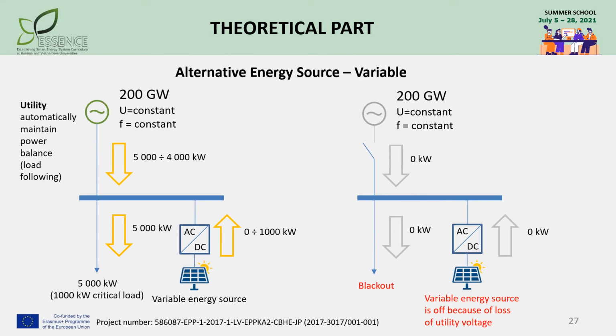If we want to benefit from a variable renewable source, then in case of grid-connected operation, its output fluctuations will be covered by the utility. The microgrid will be seen from the utility side as a load fluctuating in response to the change of ambient conditions. But in case of loss of utility interface, the microgrid will be fully de-energized if the variable source has a grid following inverter because of the loss of utility voltage.